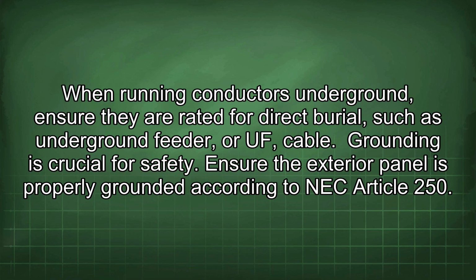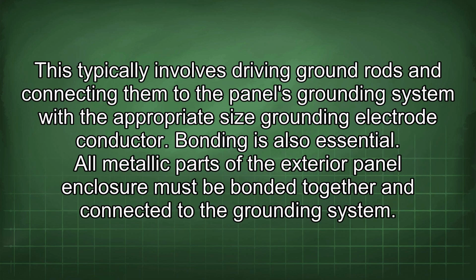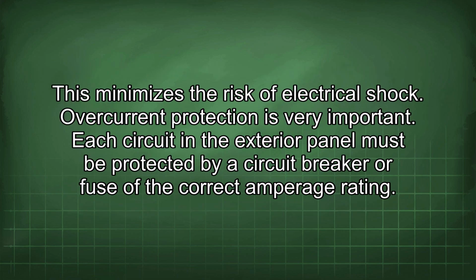Grounding is crucial for safety. Ensure the exterior panel is properly grounded according to NEC Article 250. This typically involves driving ground rods and connecting them to the panel's grounding system with the appropriate size grounding electrode conductor. Bonding is also essential. All metallic parts of the exterior panel enclosure must be bonded together and connected to the grounding system. This minimizes the risk of electrical shock.